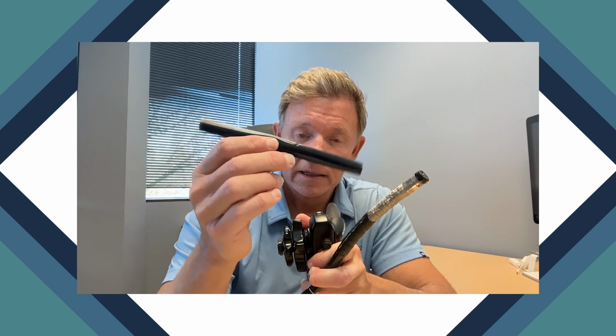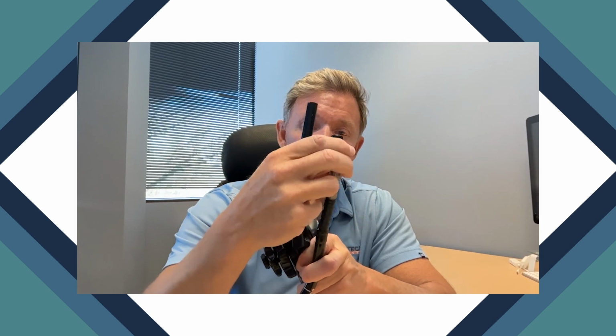One thing to keep in mind, and I don't think we're going to spend a lot of time on leak testing on this particular episode, but when the user is leak testing the scope, you do want to angulate the tip like this in all 4 directions. The reason you want to do that is because this is a rubber material, and many times you might have a pinhole in this rubber sheath, and if you just keep this distal end straight like this, you don't see the leak. Not until you angulate it will you stretch the rubber, open up the hole, expose the leak, and then you'll start to see it. So many leaks and pinholes are missed because of improper leak testing and not angulating that tip.